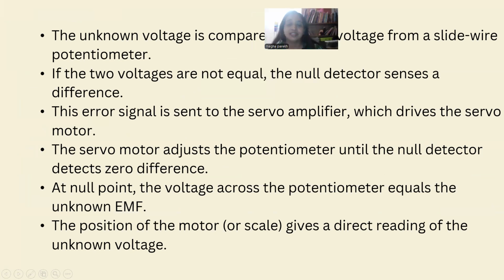The unknown voltage is compared with the voltage from a slide wire potentiometer. If the two voltages are not equal, the null detector senses the difference. This difference is known as the error and it is sent to the motor. The motor adjusts the potentiometer until the null detector reads zero. At the null point, the voltage across the potentiometer equals the EMF. The position of the motor gives a direct reading of the unknown voltage.